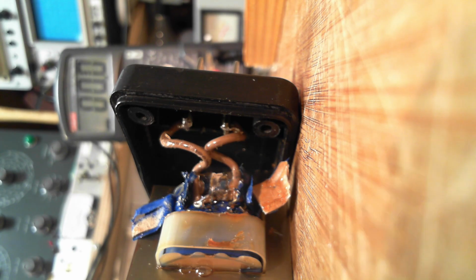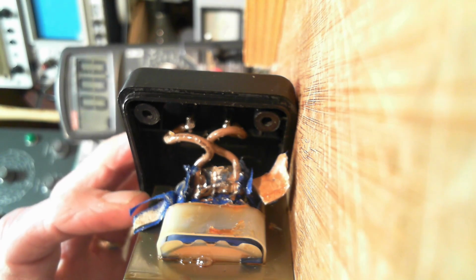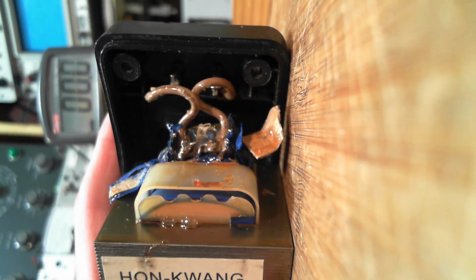The issue with power is temperatures. The equipment has current ratings on it, but those ratings are almost always based on what the temperature is going to be for the item operating. Sometimes they give a rating and state a certain ambient temperature, or they'll give you a temperature rise over ambient. So the issue is temperature.